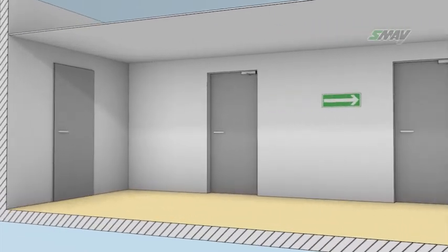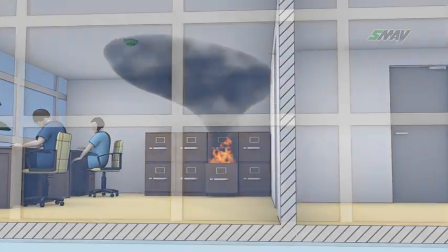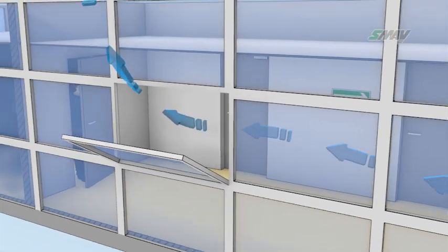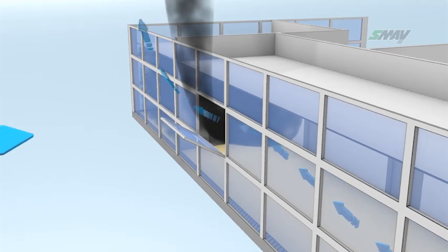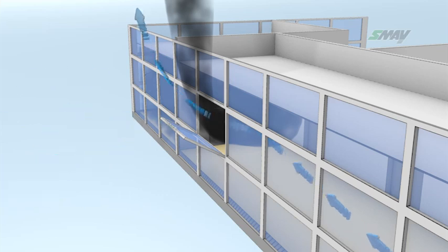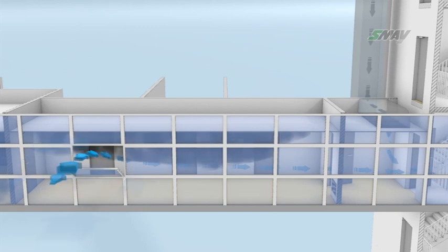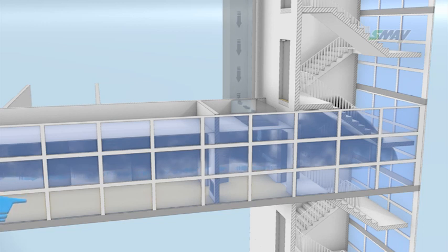Designing appropriate air release in the corridor will ensure that the smoke will be extracted from the corridor. Air may be extracted by a mechanical smoke extraction installation or naturally, for example, window ventilation may be used. The detrimental effects of external factors should be taken into consideration if using natural ventilation. For example, strong wind blowing at right angles to the facade with the window may cause a zone of overpressure, which will, if the doors between the corridor and the stairwell are opened, prevent effective extraction of the air and smoke mixture. As the air and smoke is not being extracted, it may flow into the stairwell.